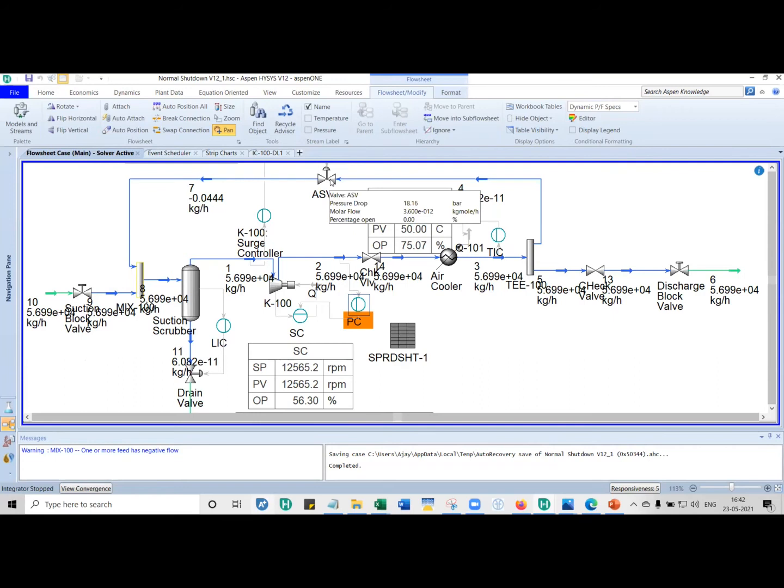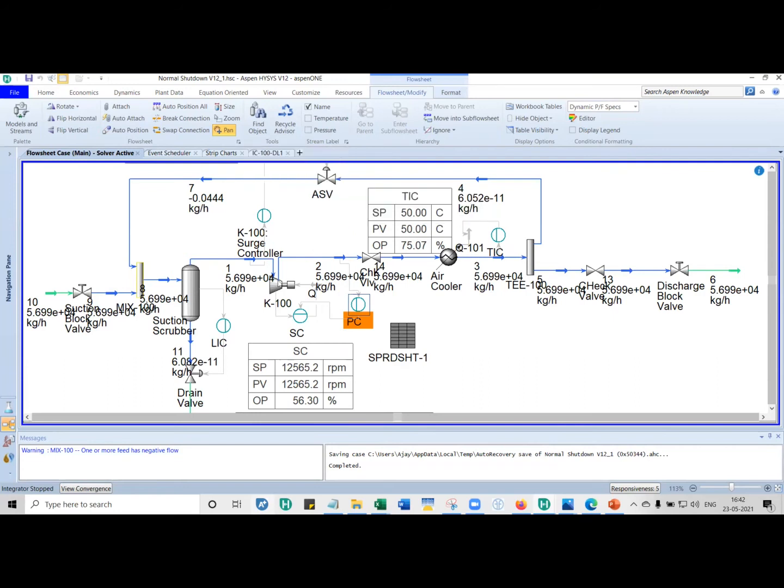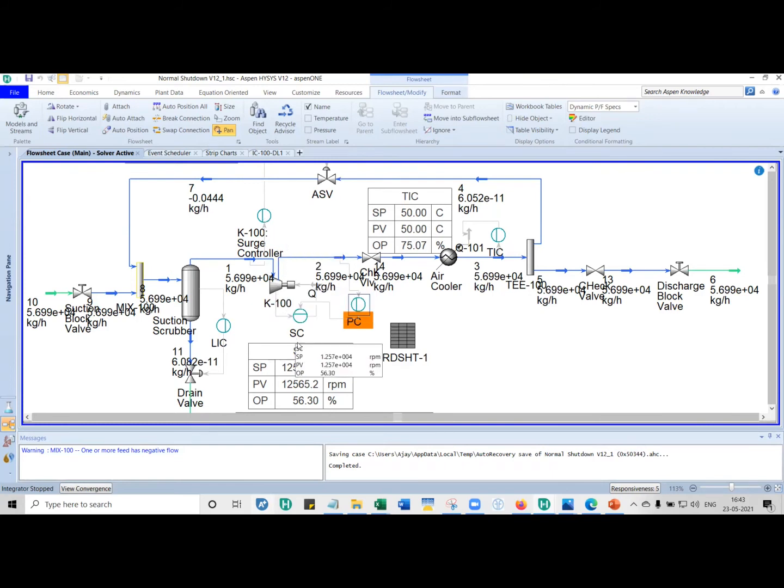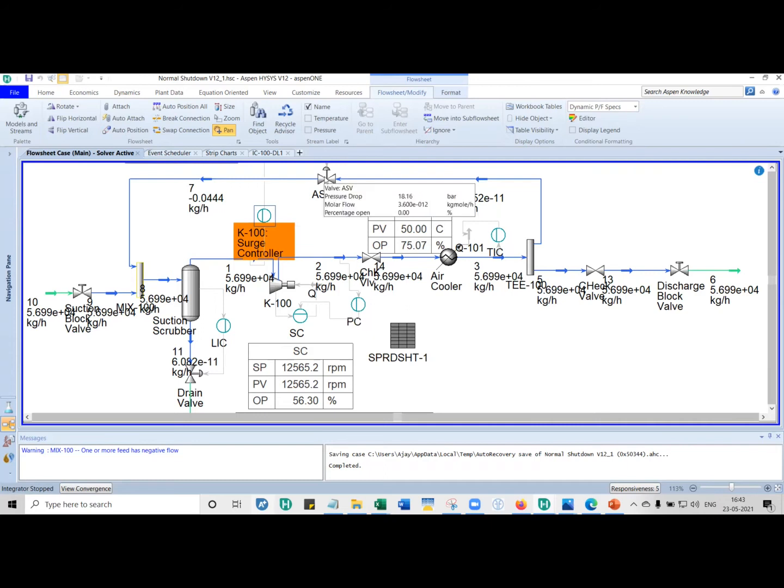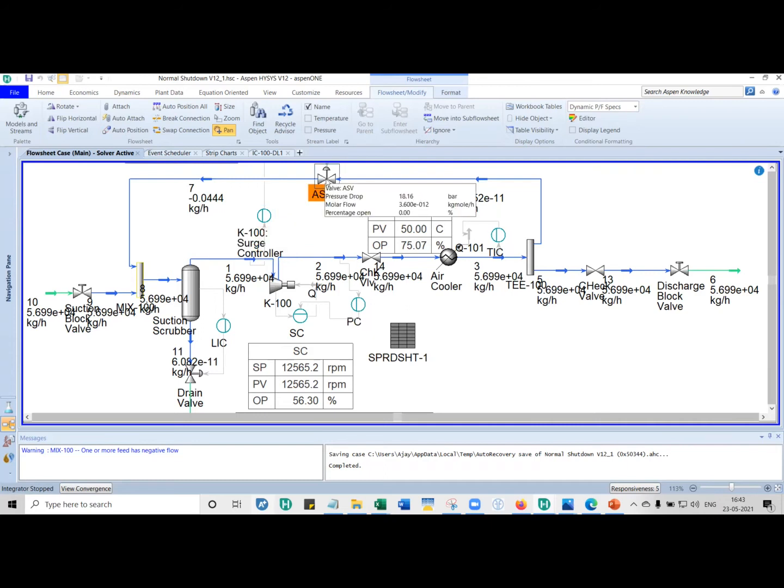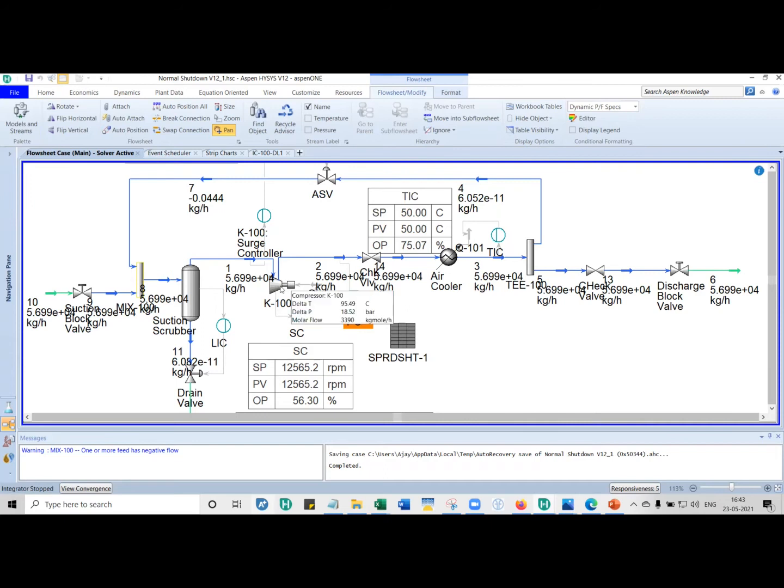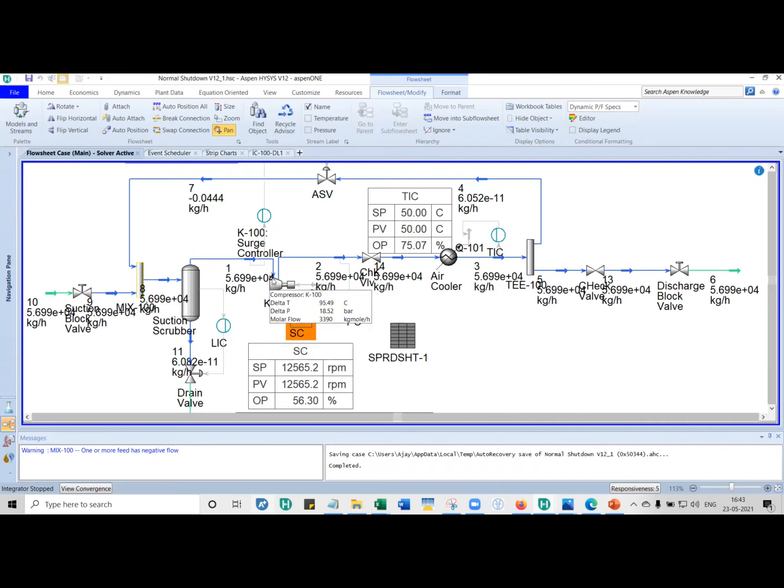The next thing is, let's say the compressor was tripped. When the compressor has tripped, the controller is still trying to function. In a normal shutdown, what we do is open the ASV completely 100% open, and then we trip the compressor. If the surge controller is still functioning, then as the compressor is starting to coast down, this controller will try to keep closing the anti-surge valve. We don't want that to happen. So we must disconnect the controller from messing around with the anti-surge valve.